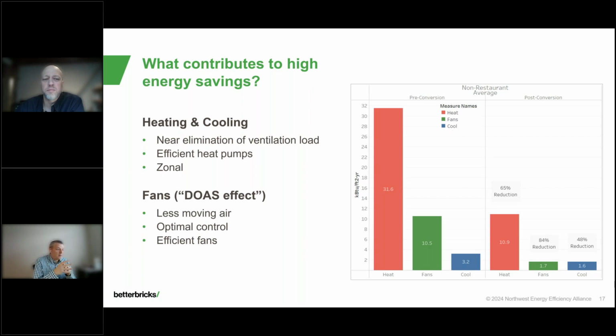Then there's the fans, the DOAS effect. Using high efficiency fans with outside air, you move less air, optimize the controls, and with efficient fans you get an 84% reduction in fan usage. That's a big deal, a lot of energy use right there. This is where the savings are coming from.